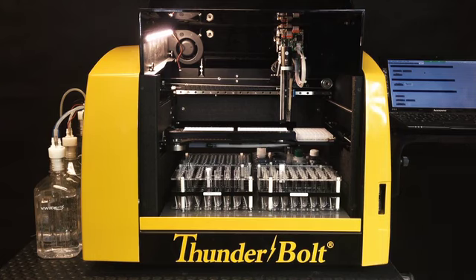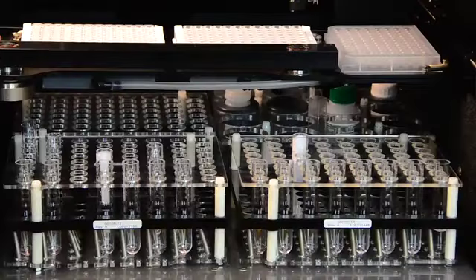We recommend that in the weekly maintenance you perform that alignment. Therefore, you're guaranteeing that throughout the week you have a nicely aligned instrument. However, many of our sites actually do their alignments at much longer time intervals. But like I said, we recommend once a week. And to me, the best part of that feature is that you have the ability to do the alignment yourself. Therefore, if something gets bumped and something does go wrong, you can realign it and get up and running again.